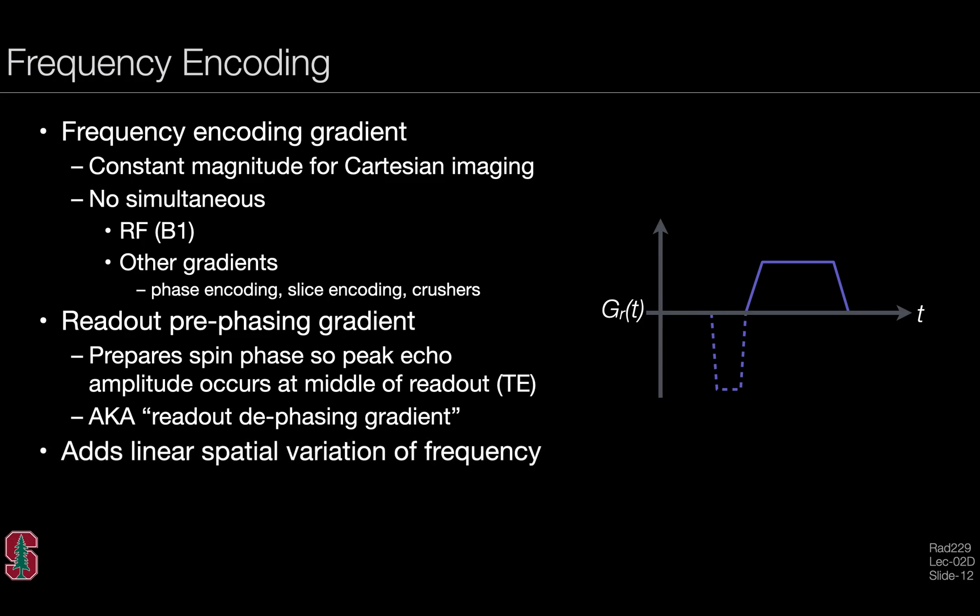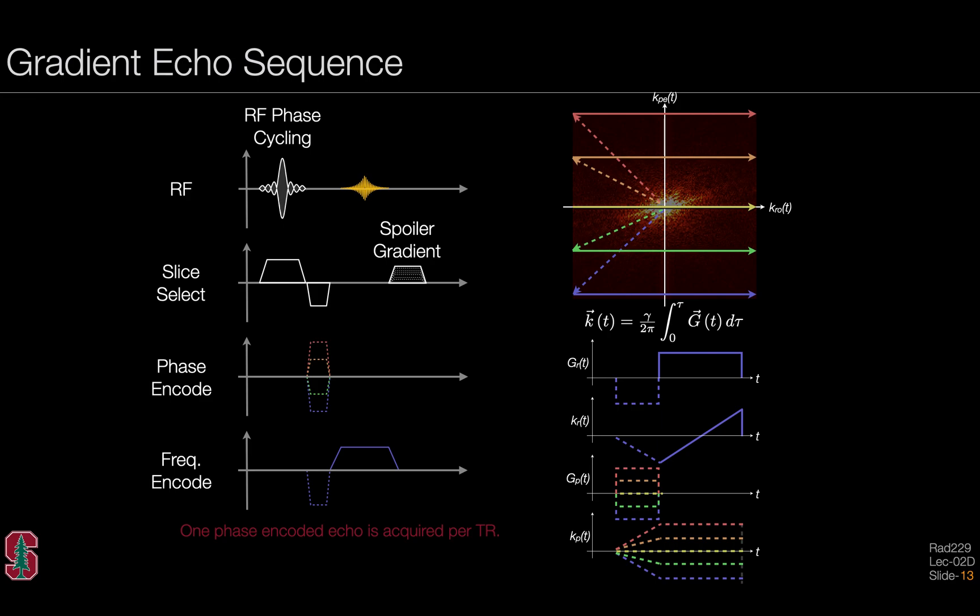The readout gradient itself adds a linear spatial variation in frequency across the object. And we use this for mapping out the spatial frequency content of the underlying object. And of course, it helps us form an echo, which we record using the coils and receiver system. This is a gradient echo sequence with slice-selective excitation, phase encoding, and the readout gradient. The readout pre-phaser helps prepare the spin phase and move us across k-space so that during the readout acquisition, the readout gradient as we're moving across k-space will come through the middle of k-space to acquire a line of k-space that helps us fill in some of the k-space matrix necessary for sampling the spatial frequencies for the underlying object.